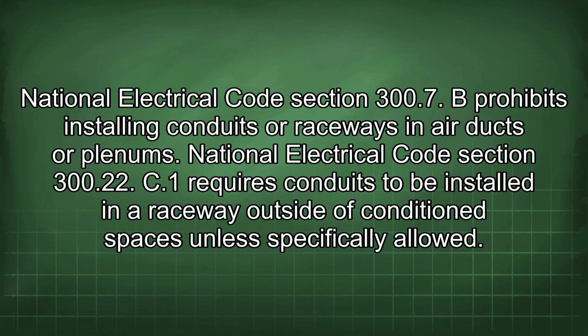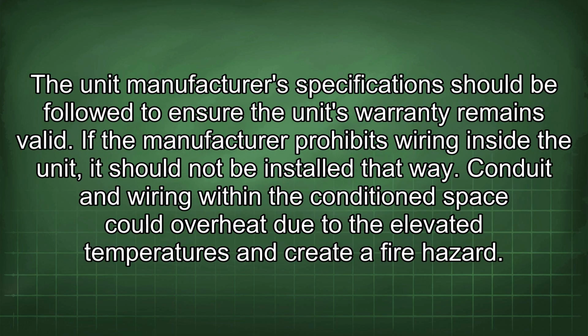National Electrical Code Section 300.7(B) prohibits installing conduits or raceways in air ducts or plenums. National Electrical Code Section 300.22(C)(1) requires conduits to be installed in a raceway outside of conditioned spaces unless specifically allowed. The unit manufacturer's specifications should be followed to ensure the unit's warranty remains valid. If the manufacturer prohibits wiring inside the unit, it should not be installed that way.